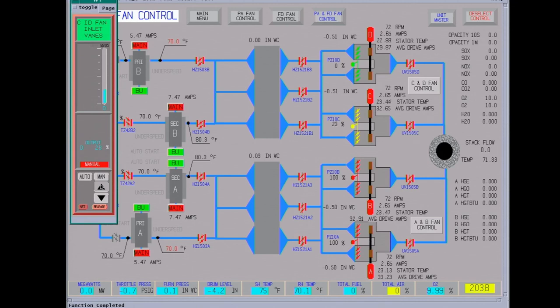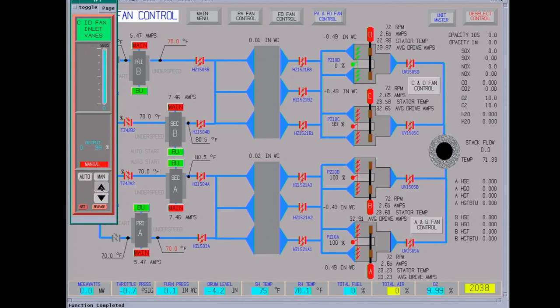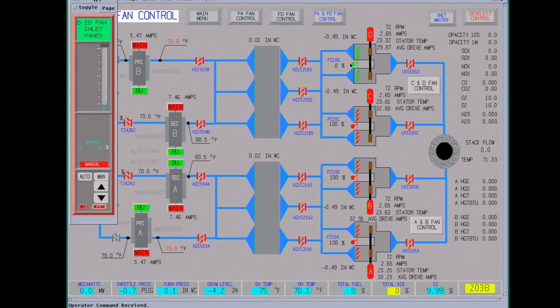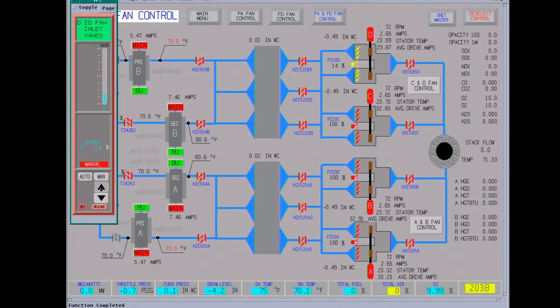We'll put this, we'll run this in manual control until we get the FD fans running. This plant will run with just three ID fans, but at a slightly reduced load. Total gas flow is around three quarter million cubic feet per minute.